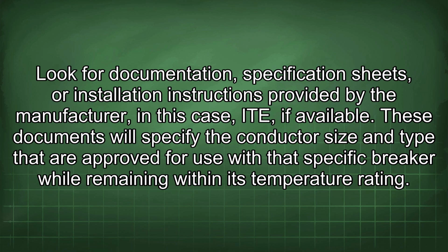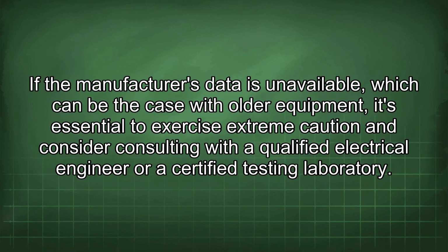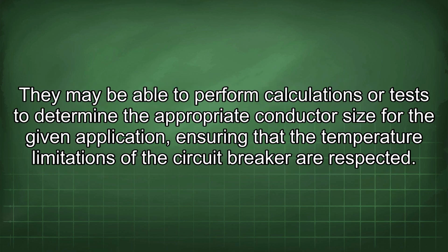within its temperature rating. If the manufacturer's data is unavailable, which can be the case with older equipment, it's essential to exercise extreme caution and consider consulting with a qualified electrical engineer or a certified testing laboratory. They may be able to perform calculations or tests to determine the appropriate conductor size for the given application, ensuring that the temperature limitations of the circuit breaker are respected.